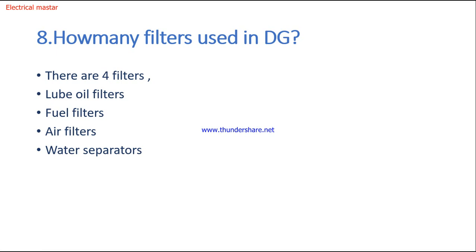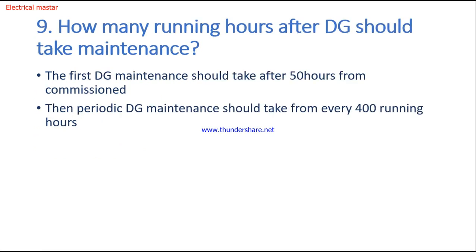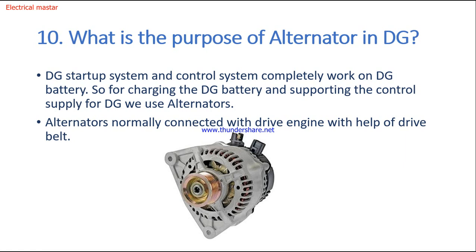Next question: how many filters are used in a diesel generator? There are four types of filters: lube oil filters, fuel filters, air filters, and water separators. Next question: after how many running hours should a diesel generator be maintained? For a newly commissioned generator, the first maintenance should be taken after 50 hours. After that, periodic maintenance should be done every 400 running hours.